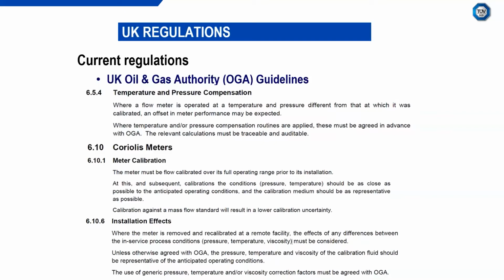So that ultimately means that you have to go to a facility such as NEL's, and others are available, maybe not with such a wide operating range, but there are plenty of other flow facilities. You have to derive a correction from a traceable facility such as NEL's. Also, the same is true for viscosity. You can see that very last line there. The use of generic pressure, temperature, and/or viscosity correction factors must be agreed with OGA. So you're really wanting to try and derive traceable correction factors and have them fully traceable and auditable by OGA if required. So the regulations do mention that there is an effect.